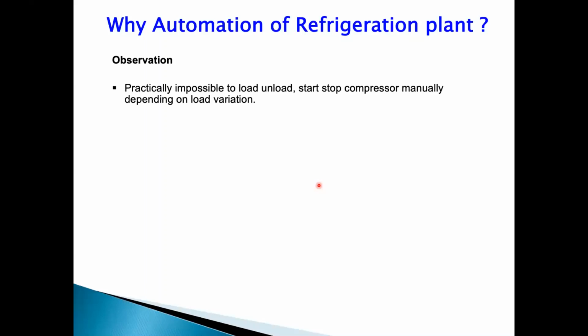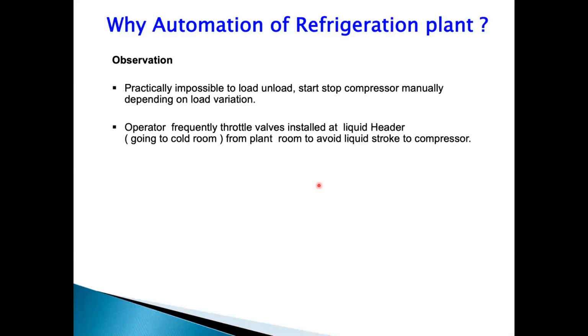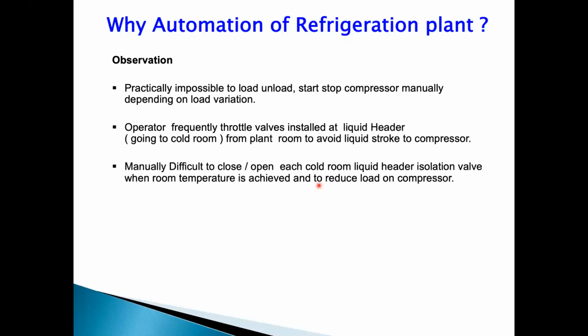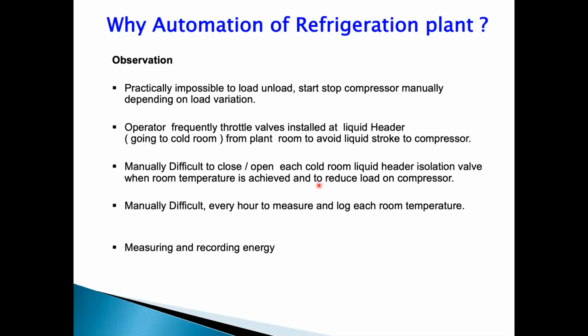Now when your plant becomes big, it is difficult to operate your compressors, start, stop, load, unload, depending on your load requirements. It is very difficult to throttle the valves at different locations. It's not possible to open and close the valves at different positions when you want to shut down or unload the compressors. Most importantly, in bigger cold storage warehouses or freezing plants, it is very difficult to record the temperatures or other parameters manually by going there every time. It's very difficult to go inside a -20 degree room and record the temperature every half an hour.